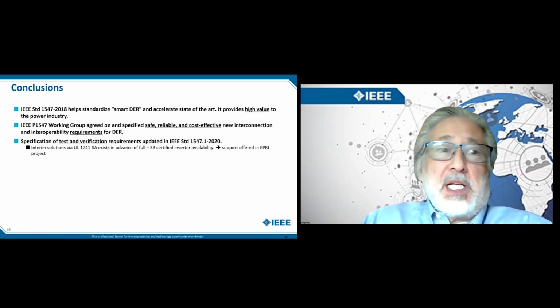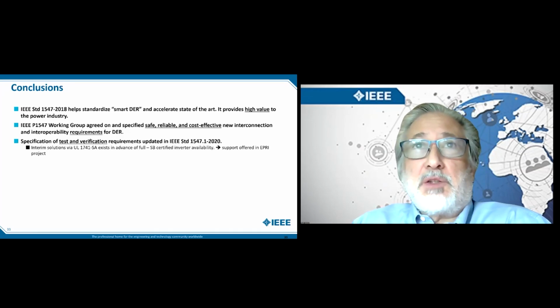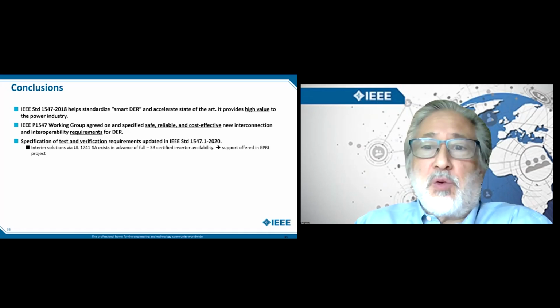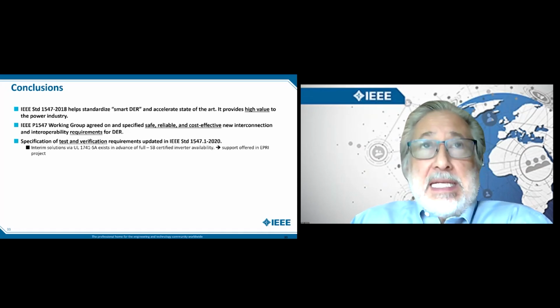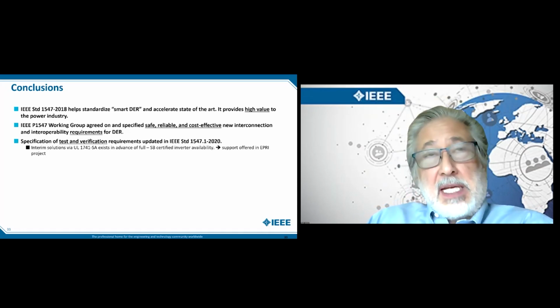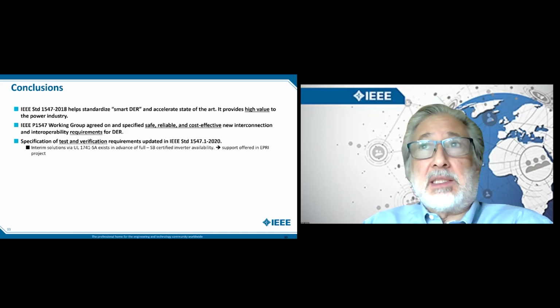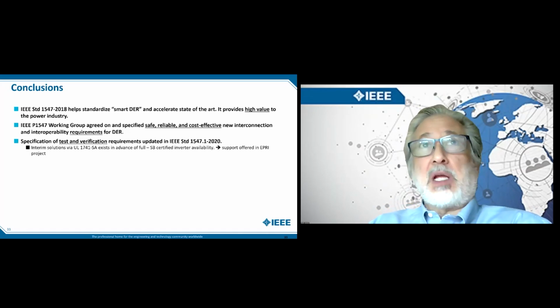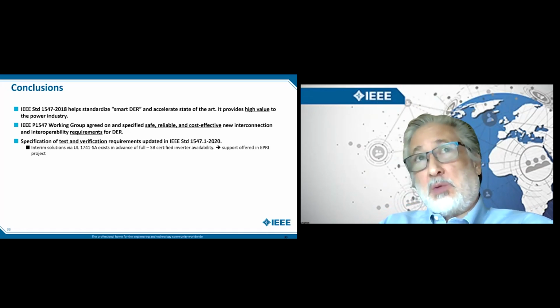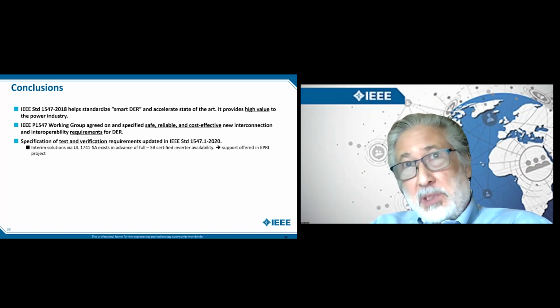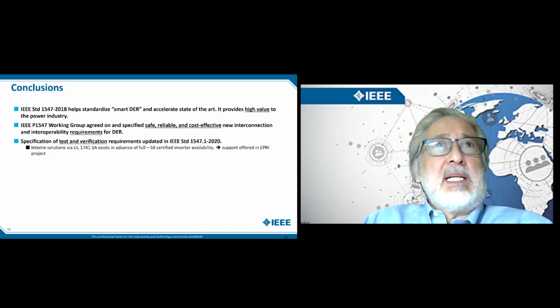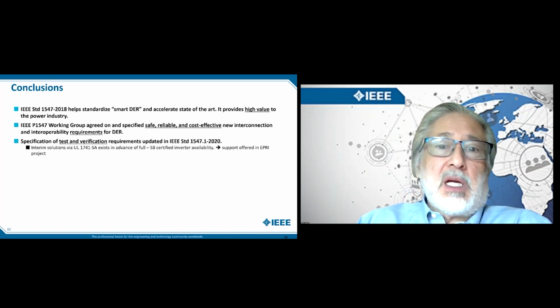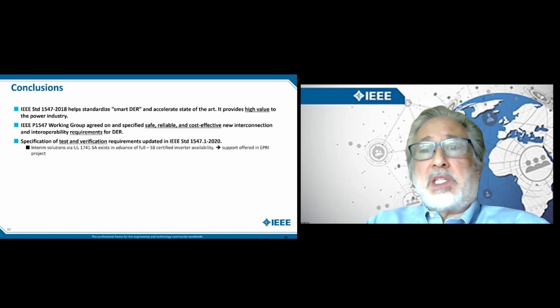This is always a challenge too. How do you verify? 1547 has a standard, 1547.1, and the base standard gives the requirements for testing. Again, it's non-prescriptive. It just broadly tells what should be tested, what ties the performance requirements to tests. The actual test procedures are called out in 1547.1.